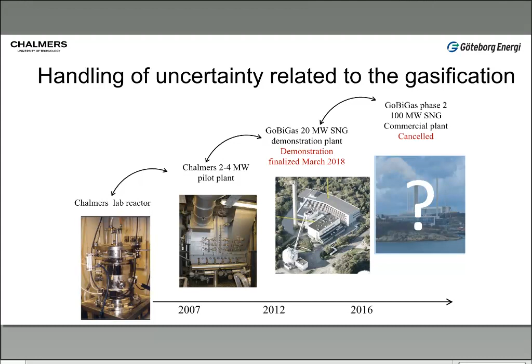Looking at the technology, it's based on the circulated fluidized bed. It's a regular boiler, we have several hundreds of them, and if you look worldwide there are several thousand of these boilers up and running. It's a regular circulated fluidized bed where you have a heat carrier, a bed material that evens out the temperature in the boiler system.